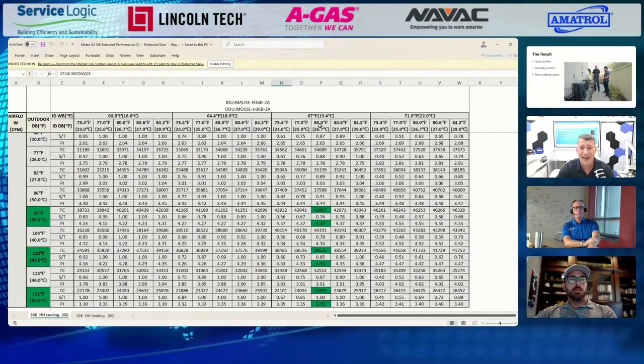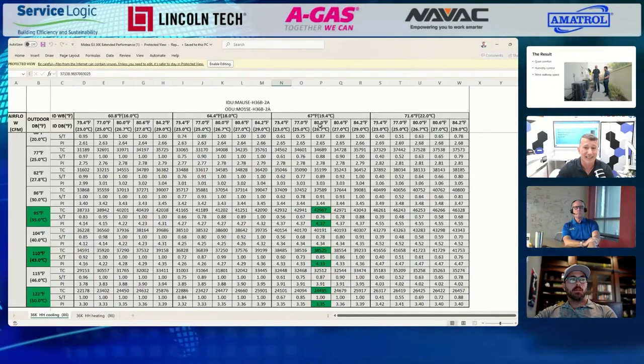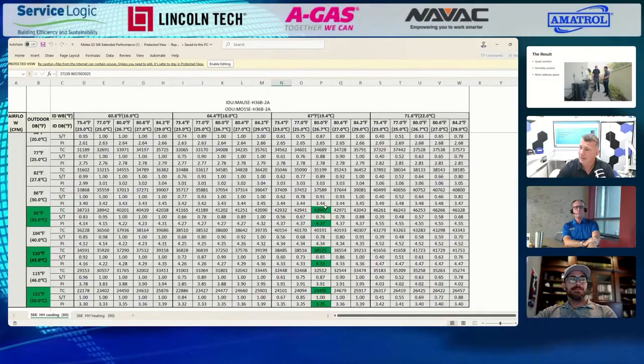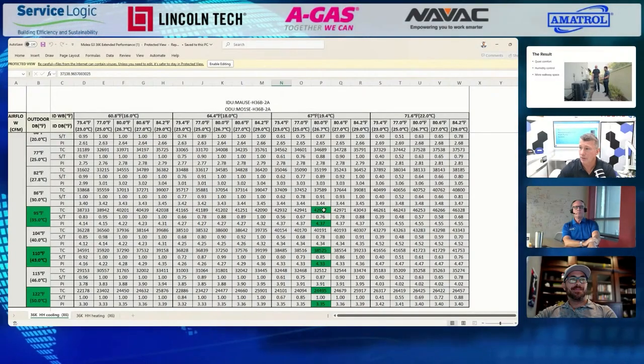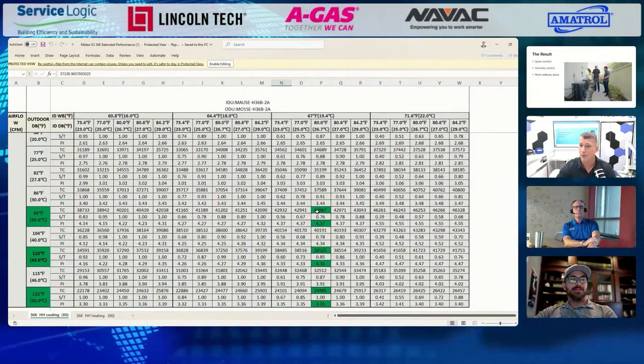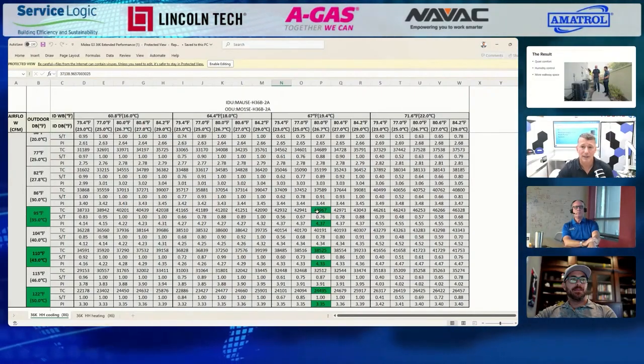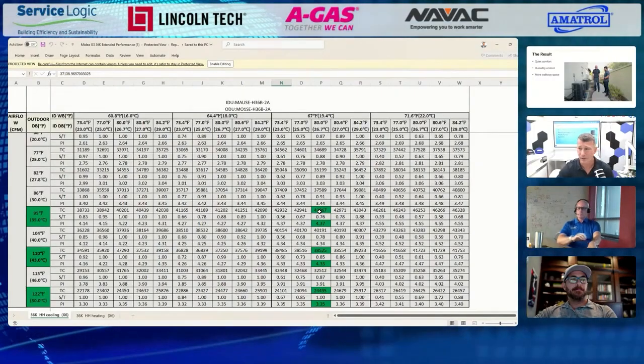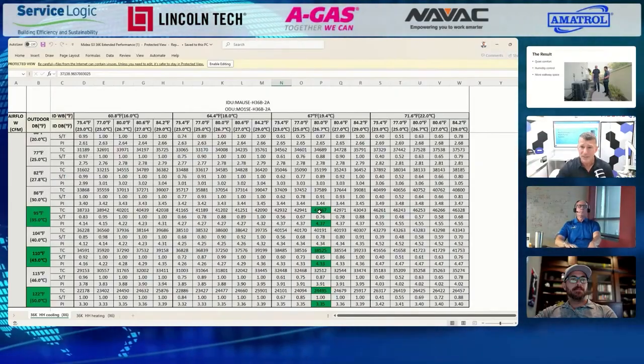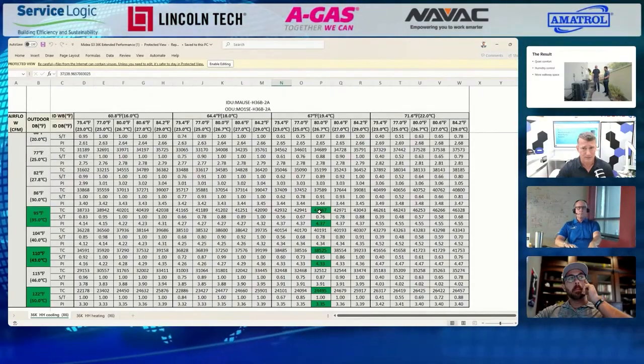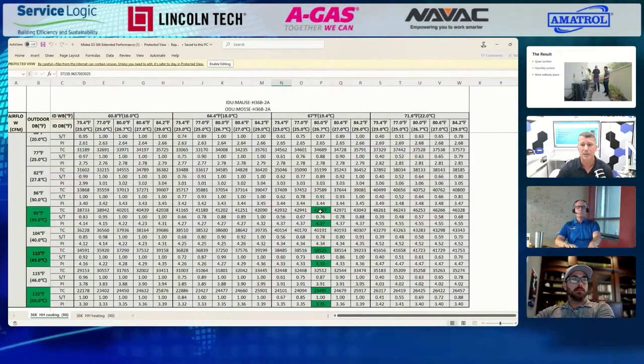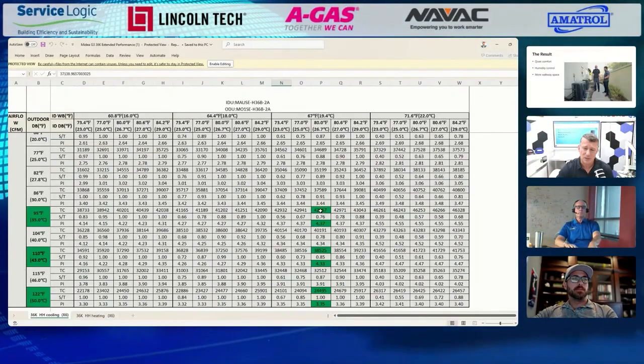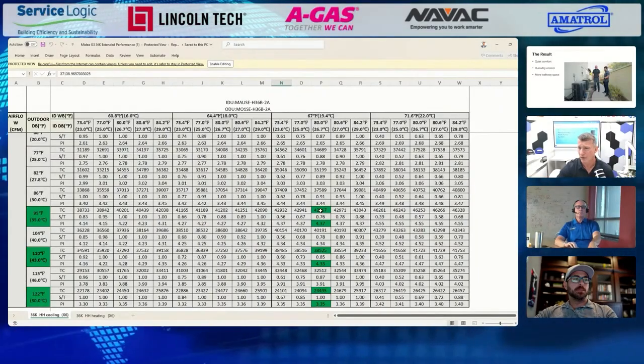If you've had setback, if you've had a bunch of kids running in and out, it's pretty realistic to fire a system up on a day and have a pretty good load on it. So now we're talking a little over 3,000, which is what's really cool with our modern inverters: with a true inverter, we can go above 100% rated, as long as our system is staying in parameters. But that's where, having the thermistors and transducers and the algorithms that are tuned properly for running, we can manage a variety of different applications.